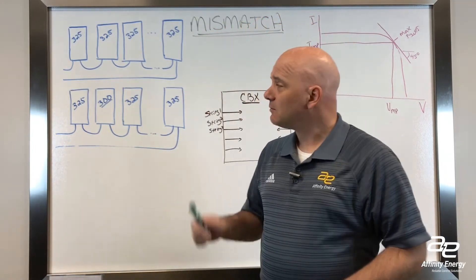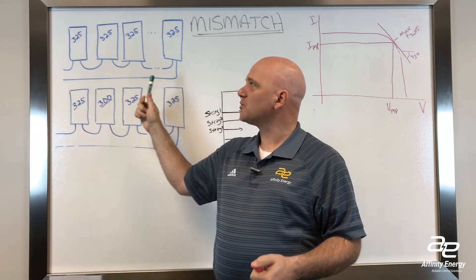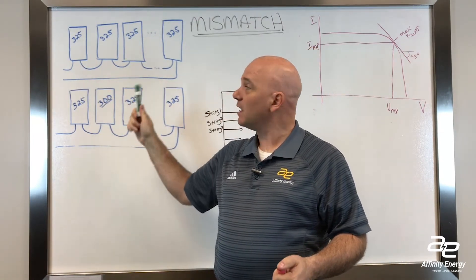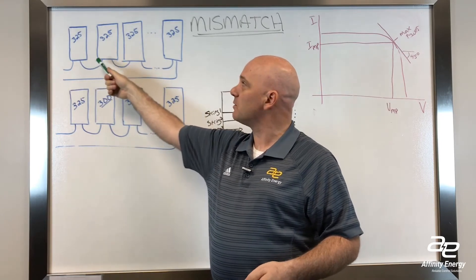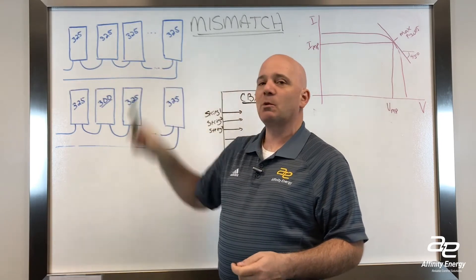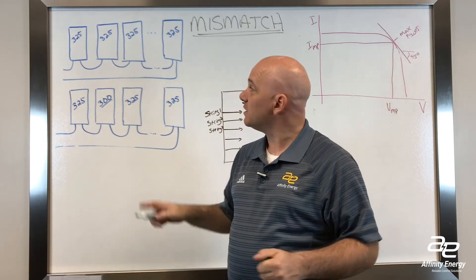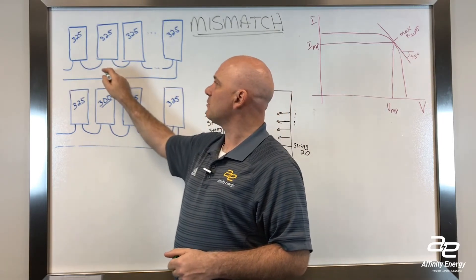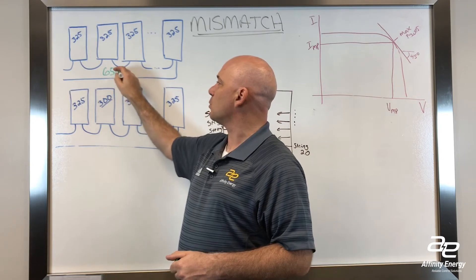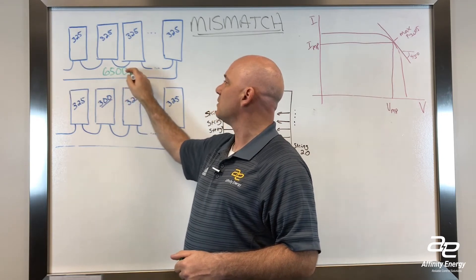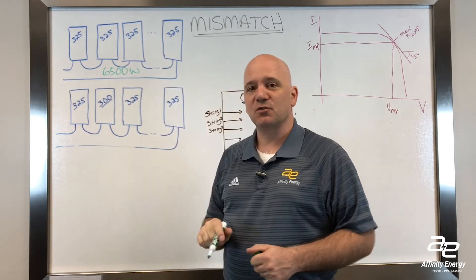The thing that I think we all know is normally you've got strings of modules wired together in series. For 325-watt modules, we've got 20 modules in a string — that makes the math a little bit easier. 20 modules at 325 watts is 6,500 watts of power from this particular string.